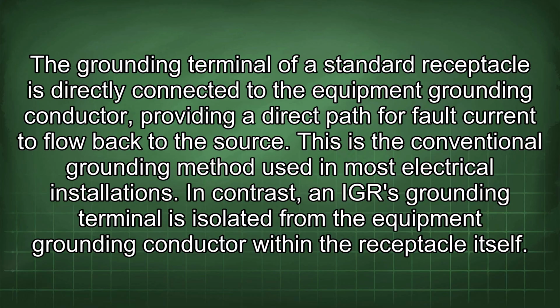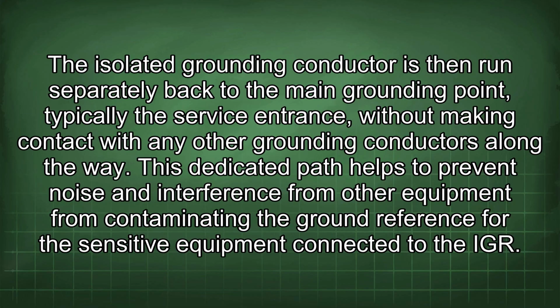In contrast, an IGR grounding terminal is isolated from the equipment grounding conductor within the receptacle itself. The isolated grounding conductor is then run separately back to the main grounding point, typically the service entrance, without making contact with any other grounding conductors along the way. This dedicated path helps to prevent noise and interference from other equipment from contaminating the ground reference for the sensitive equipment connected to the IGR.